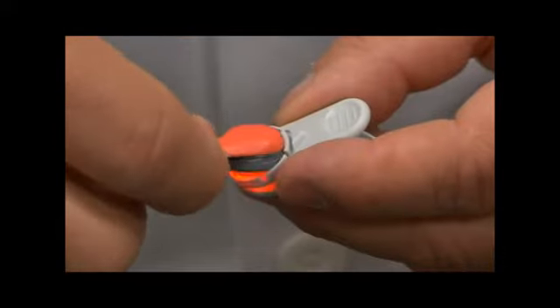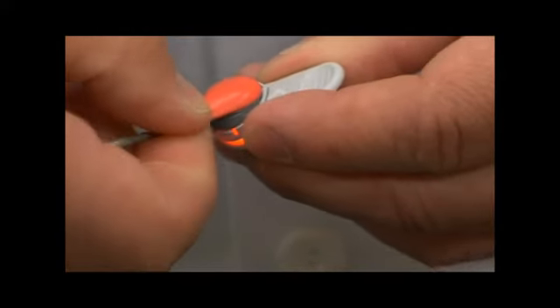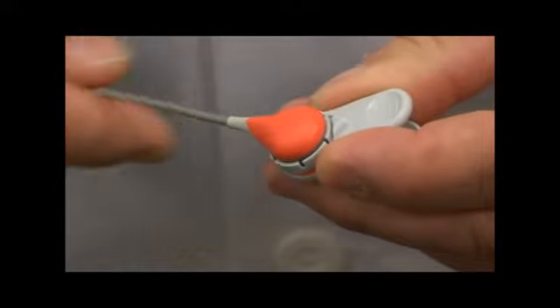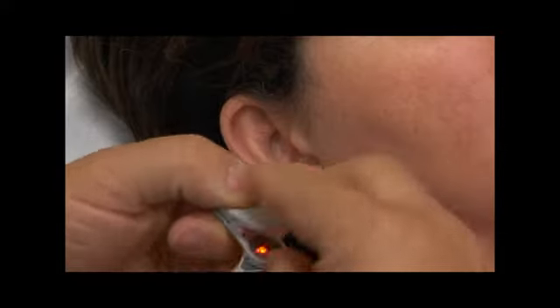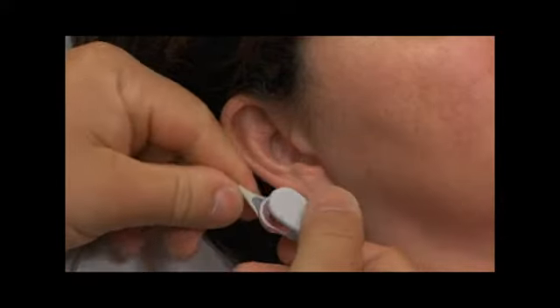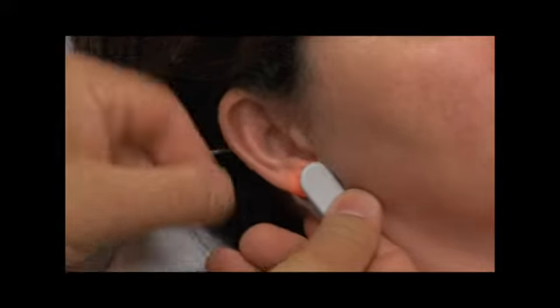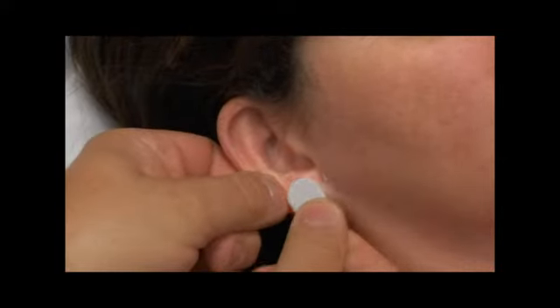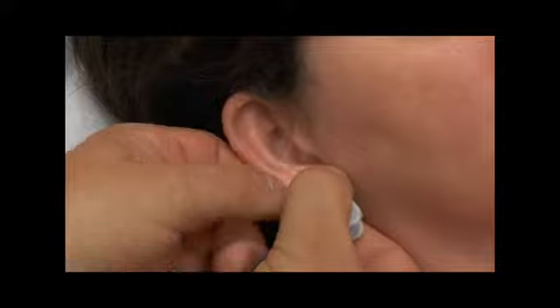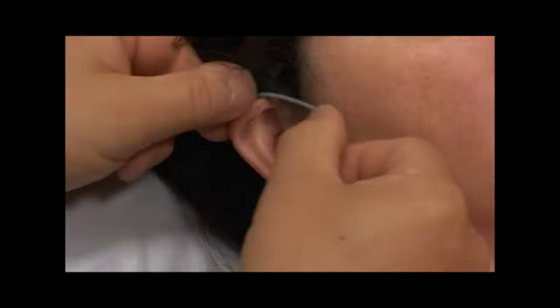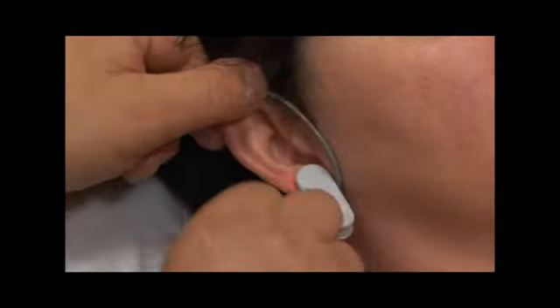Press the sensor into the ear clip until it snaps. Check that the sensor can be easily rotated to assure that it is snapped in correctly. Pull the earlobe in a horizontal position and attach the sensor from below to the back side of the earlobe. Close the clip from above, then guide the earlobe back in vertical position. The sensor is applied correctly if the whole dark surface is covered by the earlobe.